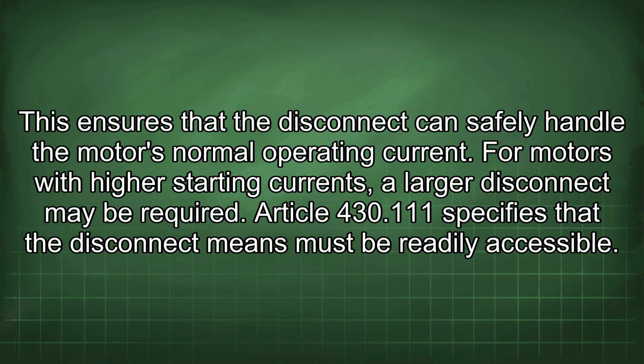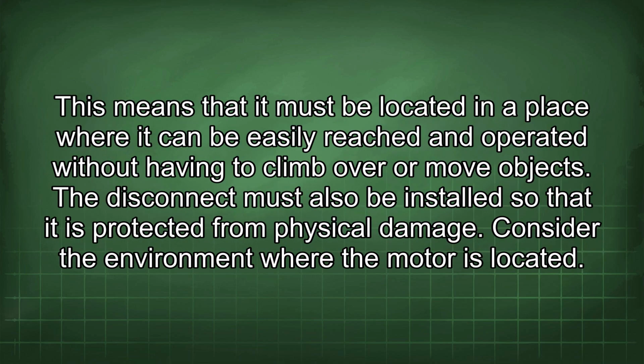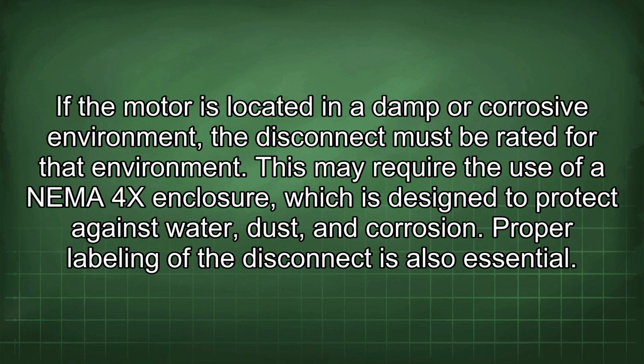Article 430.111 specifies that the disconnect means must be readily accessible. This means that it must be located in a place where it can be easily reached and operated without having to climb over or move objects. The disconnect must also be installed so that it is protected from physical damage. Consider the environment where the motor is located. If the motor is located in a damp or corrosive environment, the disconnect must be rated for that environment. This may require the use of a NEMA 4X enclosure, which is designed to protect against water, dust, and corrosion.